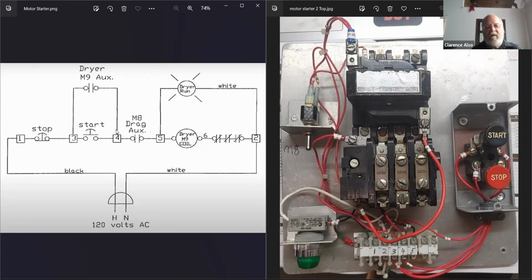So if I took this wire off right here and put my probe there at the end of that wire, maybe take it off, lock out, tag out, put another alligator clip there on your other probe, your red one, put the alligator clip on your wire. So it's disconnected there at that time, and you're just checking at the end of the wire right there, from here to here. It's not even connected there.